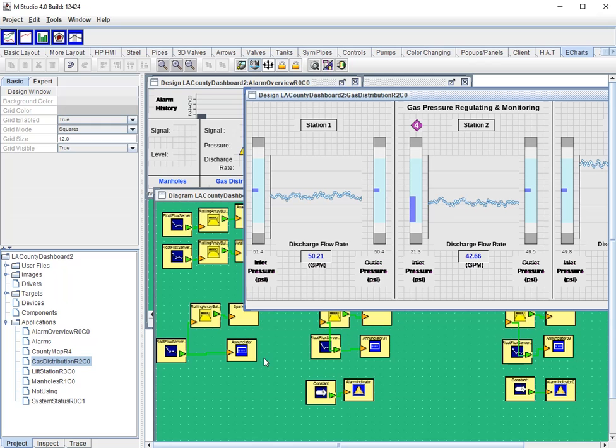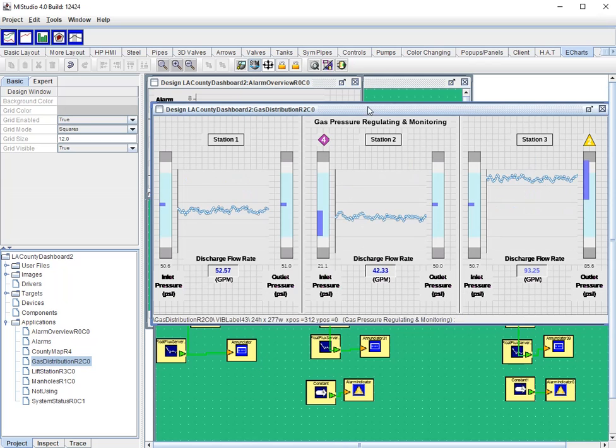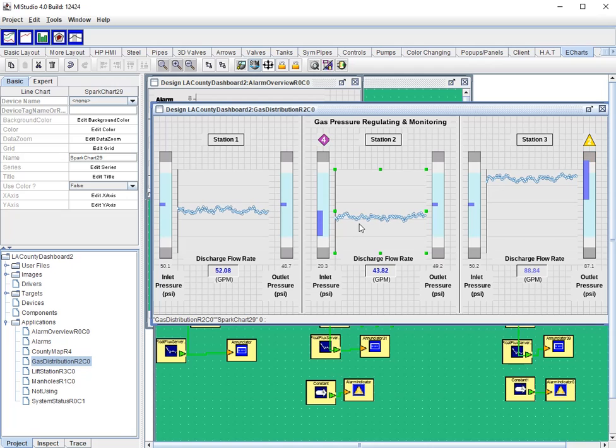Similarly, there's the idea of not just simply seeing what data we have right now, but also seeing our history data. And there are a couple of components that we use to do that. The sparkline is possibly the fundamental component of high-performance HMIs. And we can make this any size. So if we want to save screen real estate, we can make this into a tiny component, and it'll still give us most of the same information.